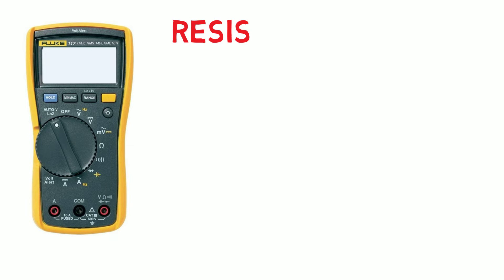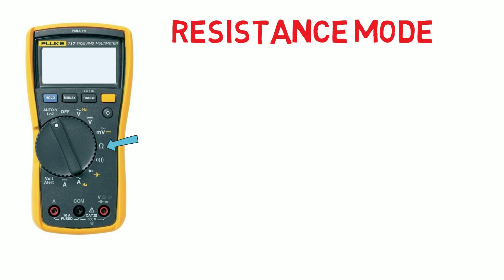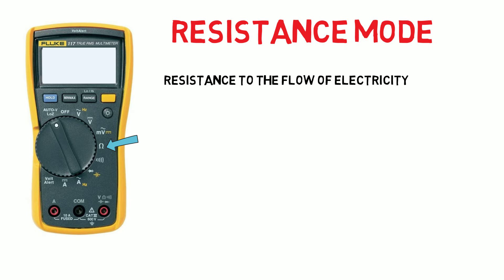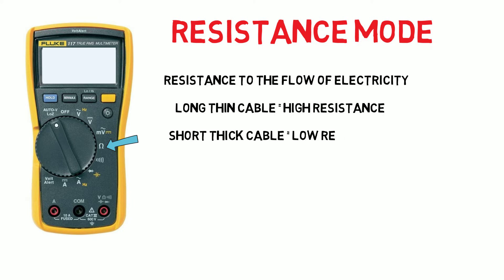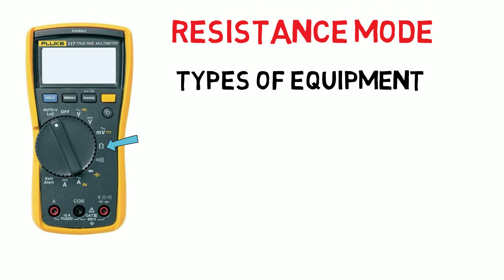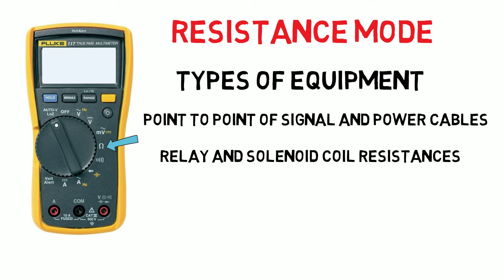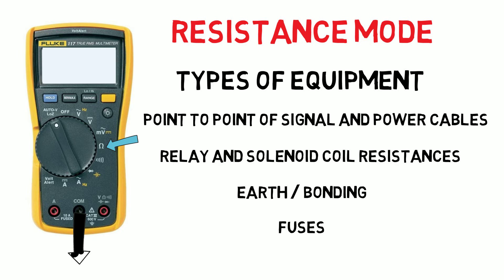We can use the meter to measure resistance, which is measured in ohms. Resistance is the measurement of the restriction to the flow of electricity — the easier the current flows through a conductor the lower the resistance. Long, low diameter cable will have a high resistance whereas a short, high diameter cable will have a low resistance. In instrumentation the types of things we would be measuring the resistance of are point-to-point signal and power cables, relay and solenoid coil resistances, resistance between earth or bonding straps, and testing of fuses. To test for resistance we need to have our probes connected to the common and ohm symbol ports. It is good practice to connect the black probe to common and red probe to the ohms connection, as when measuring voltage the polarity is important.